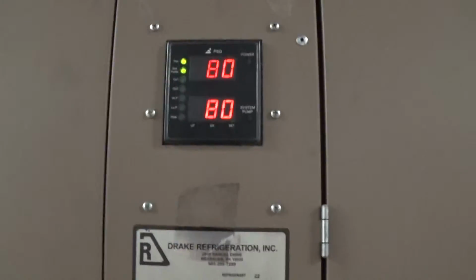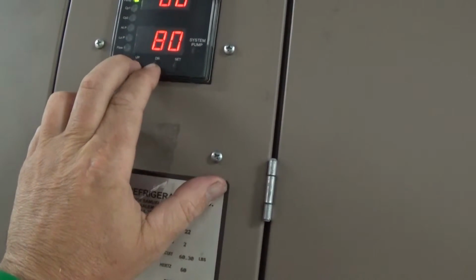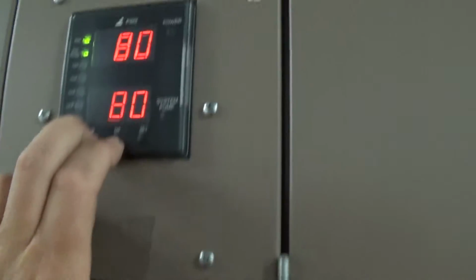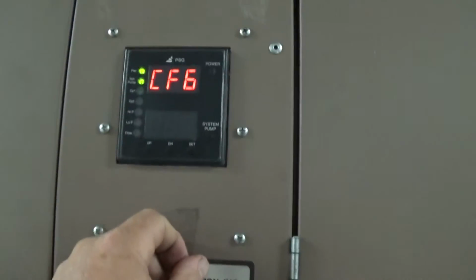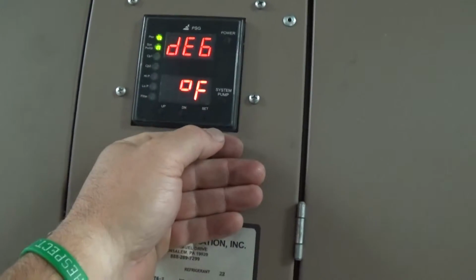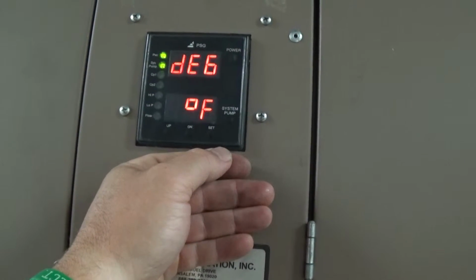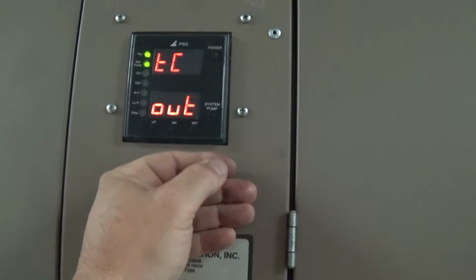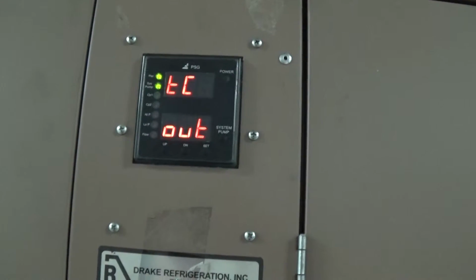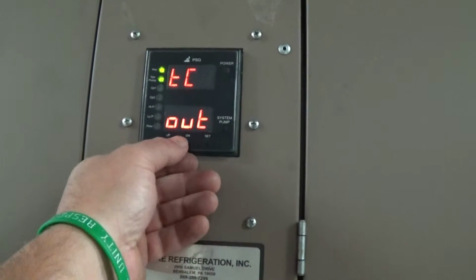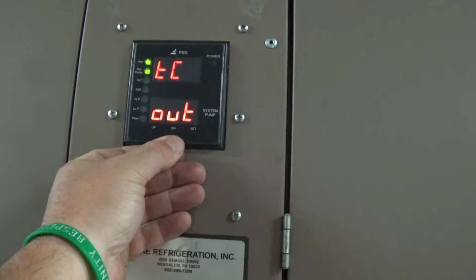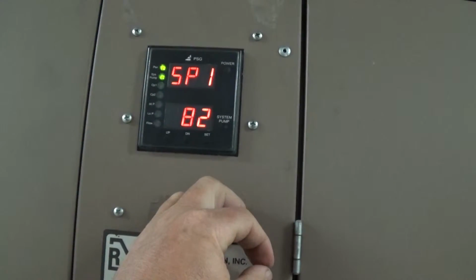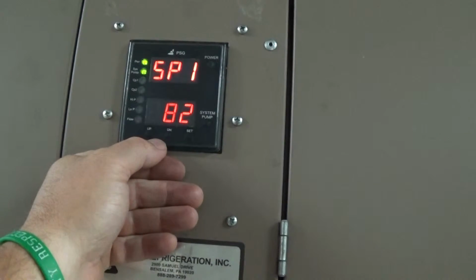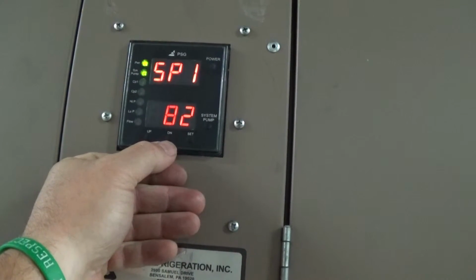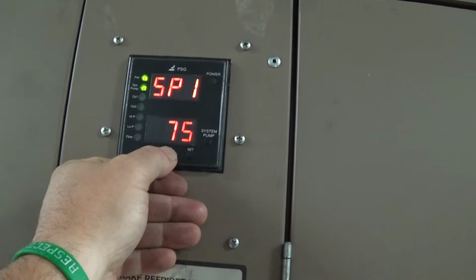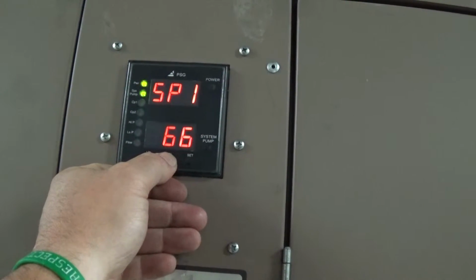So to get into the program, you press the up and down arrows at the same time. It shows CF6, then you press set, and that tells you your degrees are in Fahrenheit. You're going to press set again, and that's going to tell you that we're sensing the output temperature for our set point. So you can toggle that to in or out. Then you press set again, and you have set point 1. In this case here, we're going to chill down to 50 today. That's basically compressor 1. And for this test, we're going to set compressor 1 at 50.